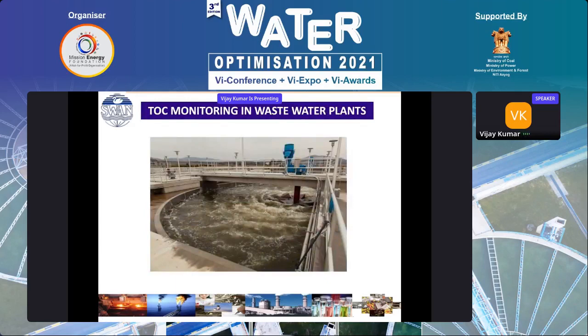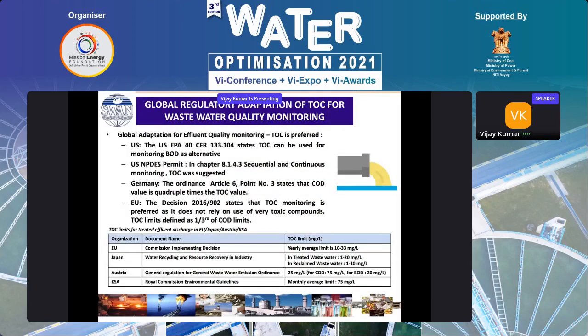The last subject is wastewater. Globally, TOC was introduced long back as an alternative to COD and BOD. Our CPCB now asks for COD and BOD online monitoring, but in fact they should have asked for TOC, since it is easy to validate and easy to know. Many countries have given limits, anywhere between 25 to 75 ppm, or you can take one third of the COD limit as the TOC limit.